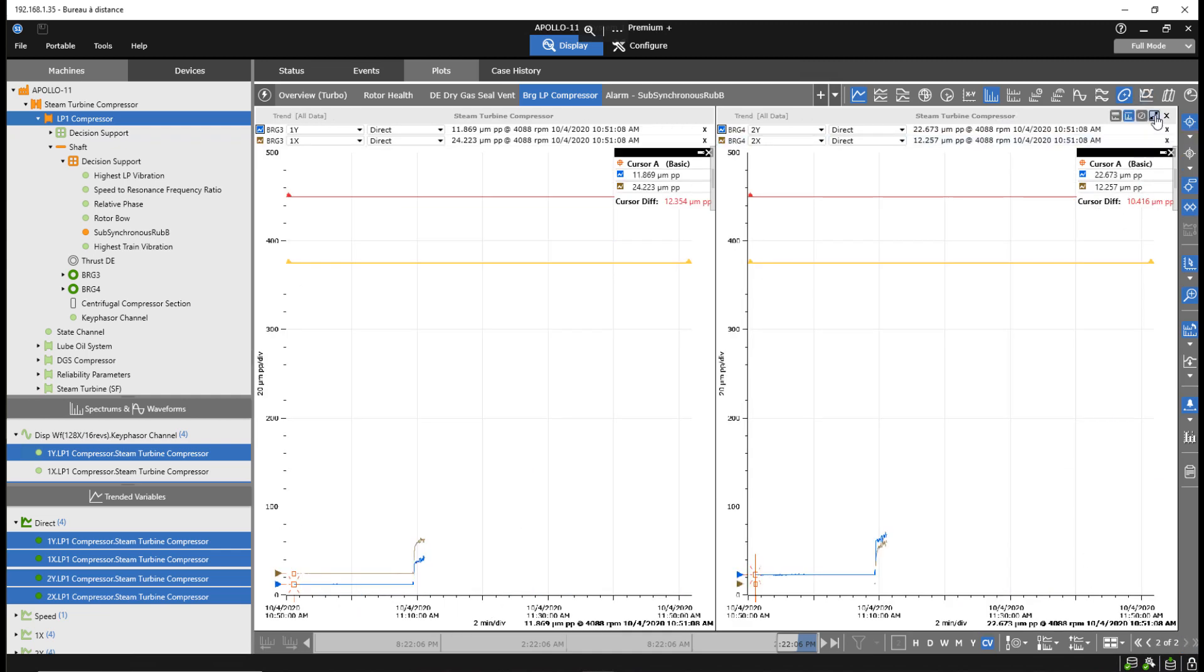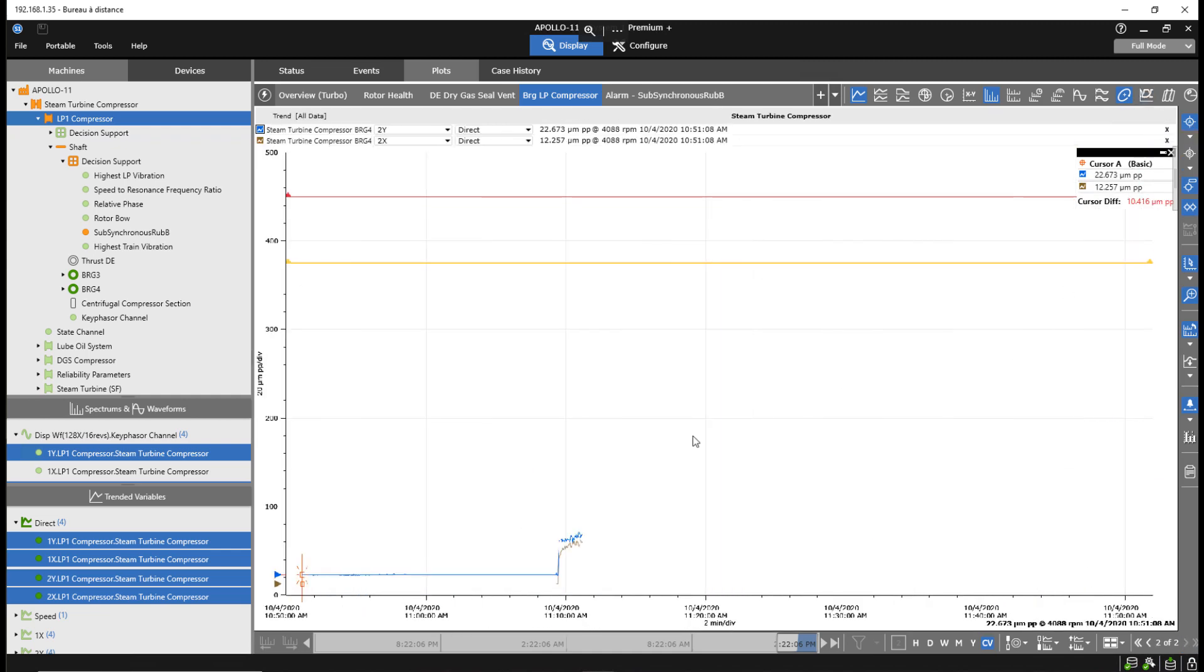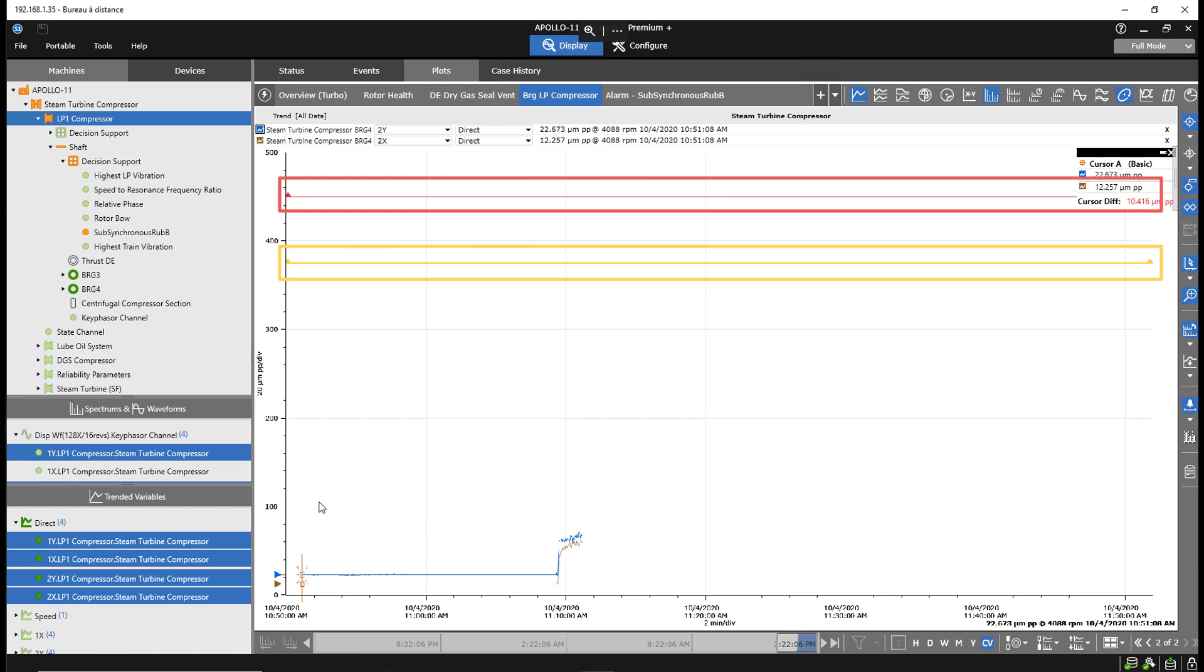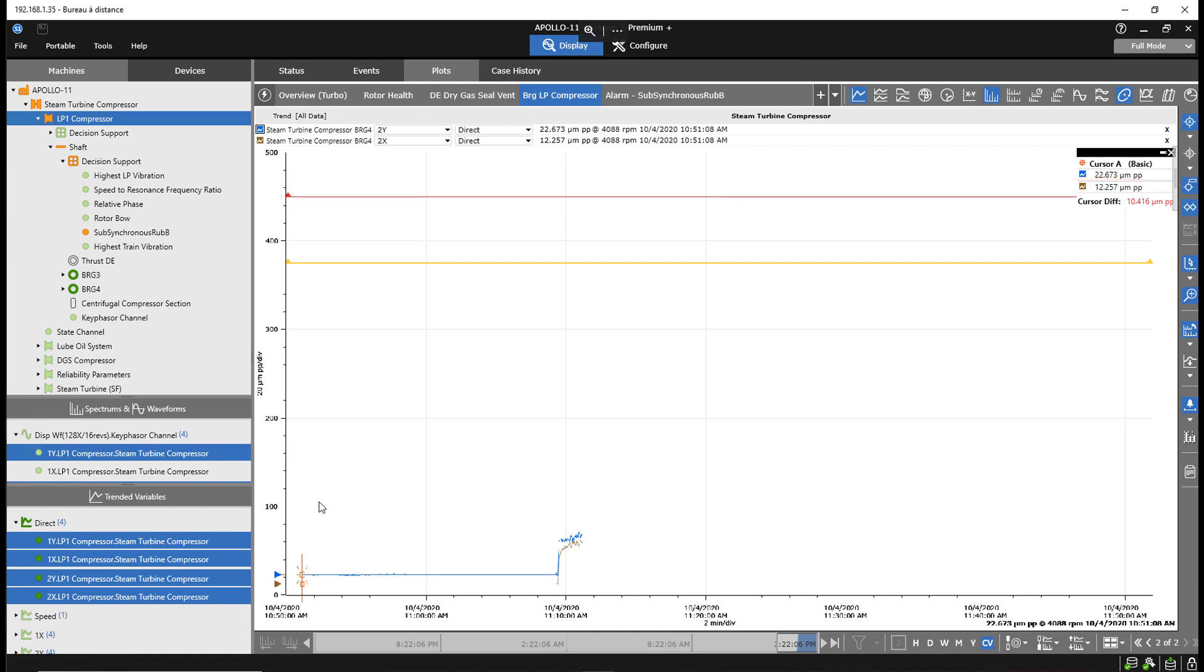By using System One with decision support, the plant staff is aware of an early change in machine behavior and can respond to this change in a timely manner. Note the yellow and red protection level set points from the Bently Nevada protection system on the trend plot. By combining System One core capabilities with decision support, plant staff are able to manage machines below protection set point levels.